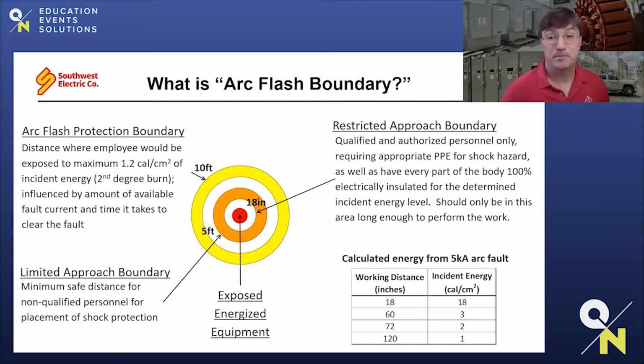So what is an arc flash boundary? This is a distance that's been calculated and determined to keep individuals within a set distance to reduce the arc energy felt to no more than that 1.2 calories per square centimeter. So that arc flash protection boundary, the outer edge of this bullseye that we show on the slide, is for your general bystander, someone who's just trying to do their job, walk past a situation, basically in their street clothes. That distance will guarantee that individual should not see more than 1.2 calories per square centimeter should an arc event occur past some energized equipment that is exposed.